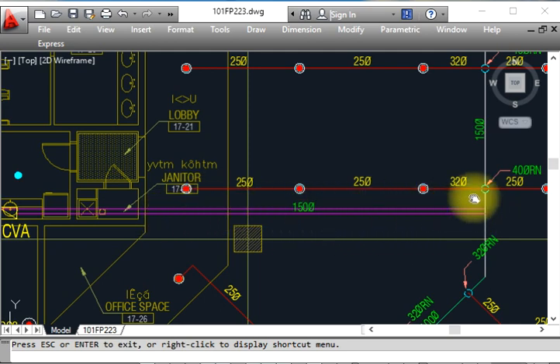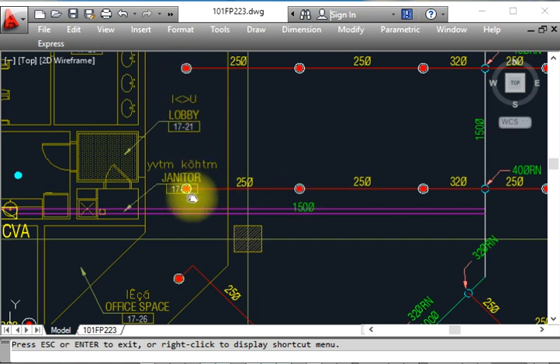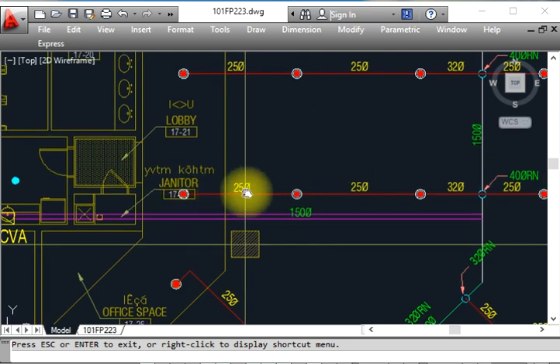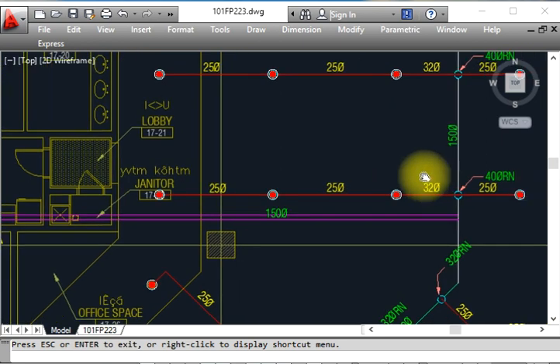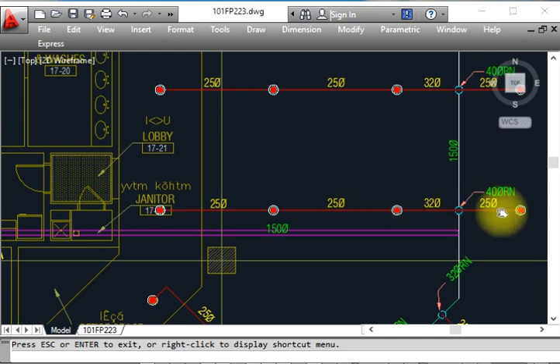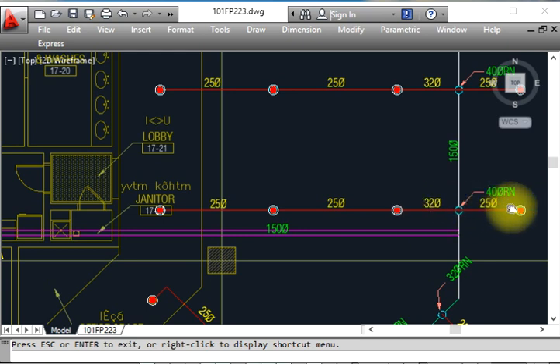This is the main pipe connecting here, and after that the white line. We provide 4 meters and 3 meters spacing. So you calculate 3 by 4 equals 12 square meters — per NFPA we need 12.3 square meters. The first pipe will be 1 inch or 25mm, the second the same, and the third sprinkler will be at 32mm. This is just per NFPA. This is the main line and the riser going up, then the 50mm will connect with this one going to 40mm because we need 32mm here and 25mm here.